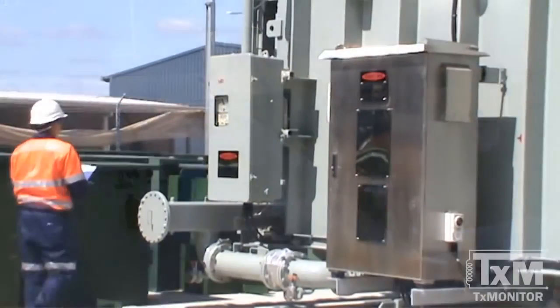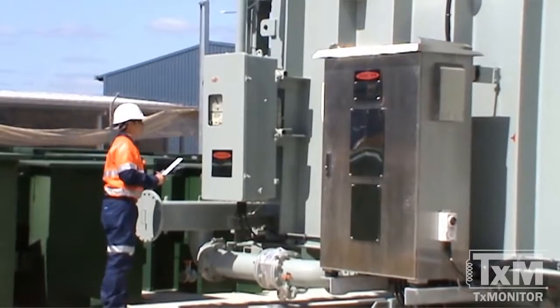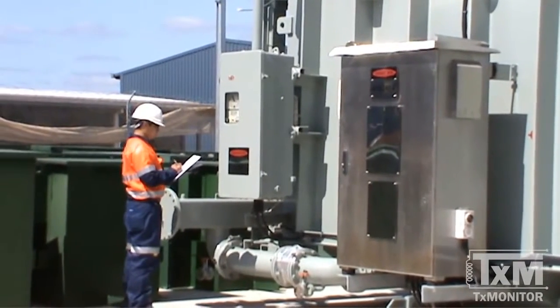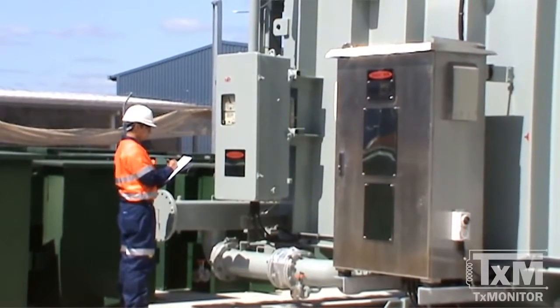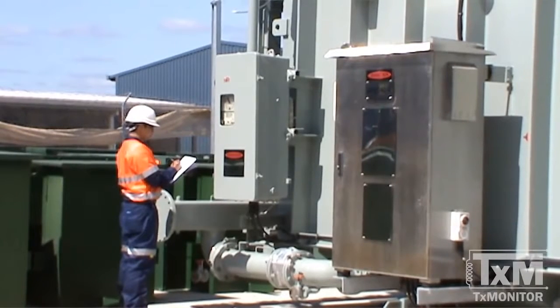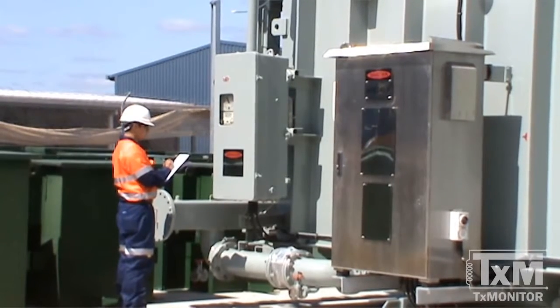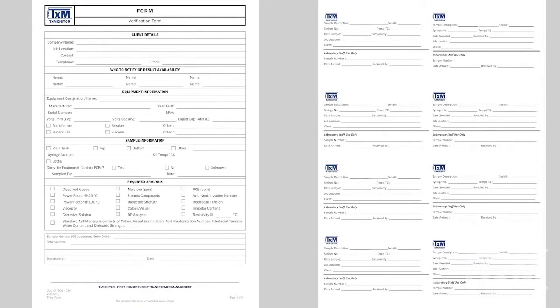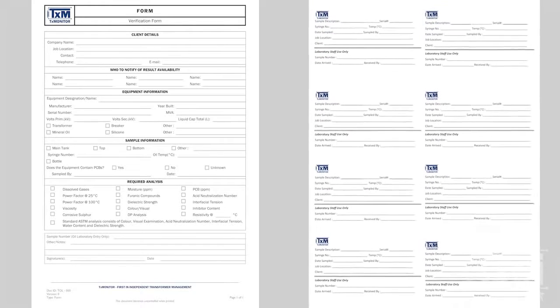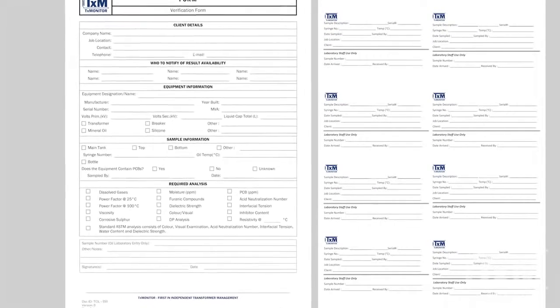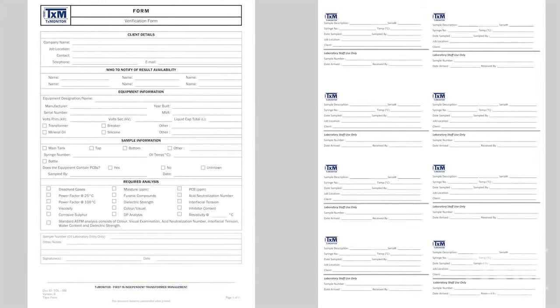The documentation process is of paramount importance during the sampling process. Critical to the sample integrity is correctly identifying and labeling of the sample being taken. There are two documents required to be filled out for each sample: the bottle label, which is affixed to the bottle, and the verification form identifying critical information about the transformer.